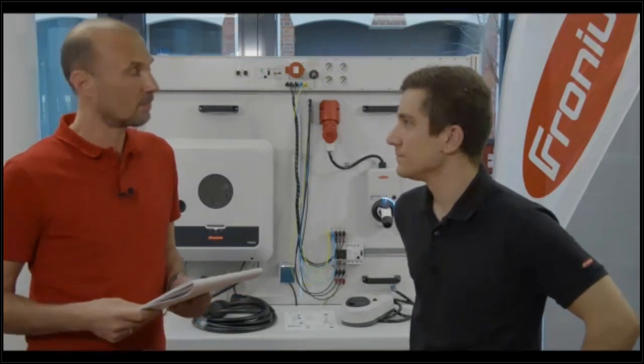Maybe you can answer. The first question was, can we use multiple Wattpilots in parallel in one PV system? Of course, you can use as many Wattpilots in one system as you want. For only charging electric vehicles, you can install multiple Wattpilots in one system. However, please note, for PV surplus charging, you can always use one Wattpilot at a time. So you always configure one Wattpilot for PV surplus charging, and for just charging, you can implement as many Wattpilots as you want. Whenever, for example, you use flexible energy tariffs, you can use multiple Wattpilots and charge your electric vehicles as cheaply as possible. But for PV surplus charging, only one Wattpilot is possible.